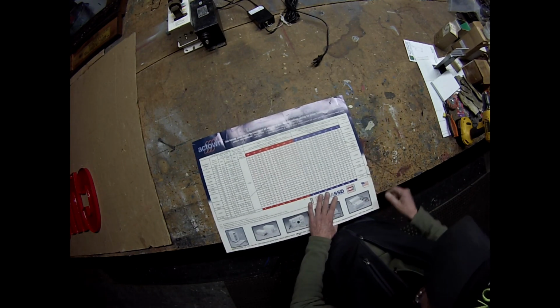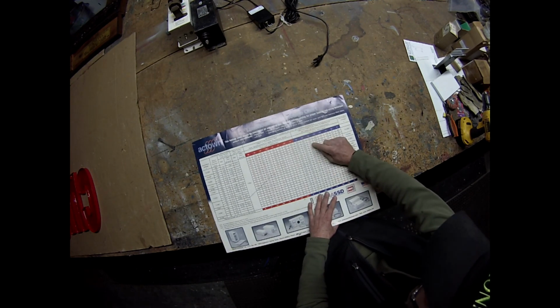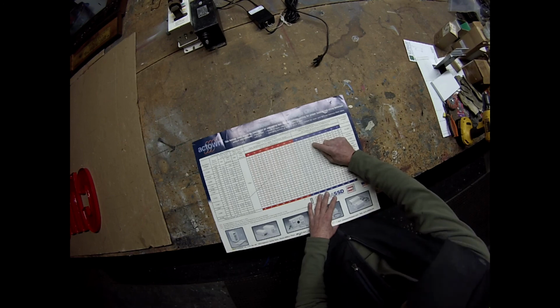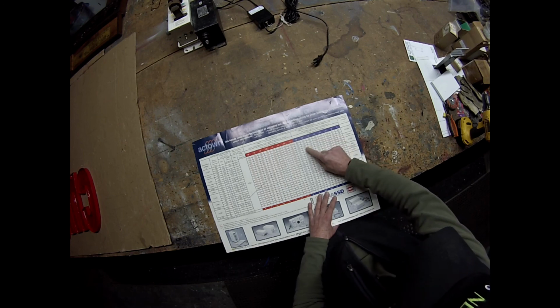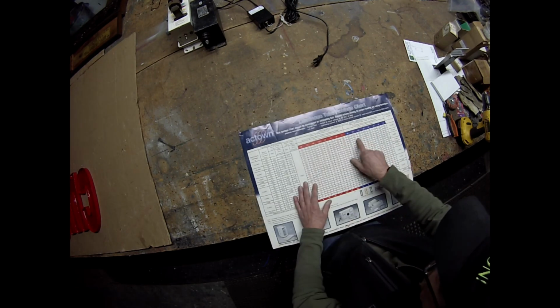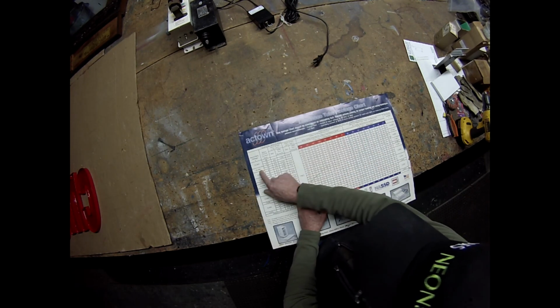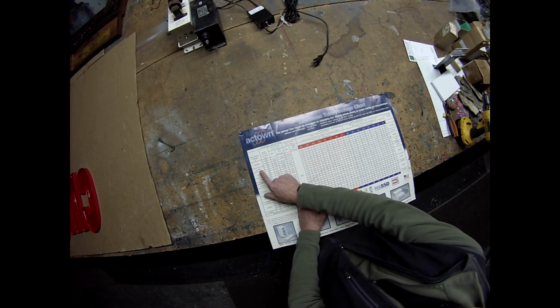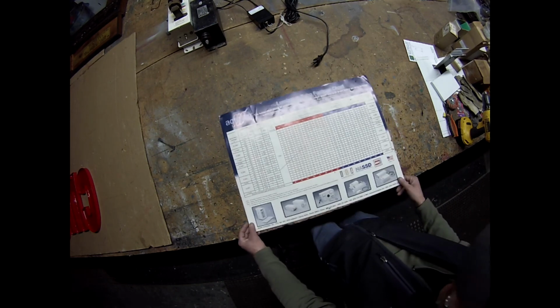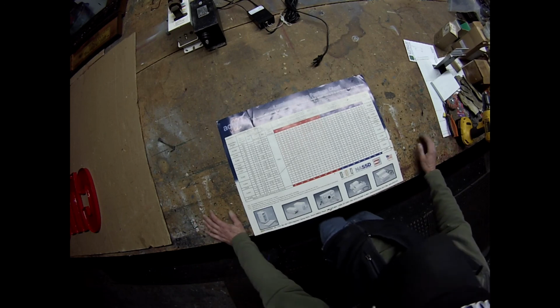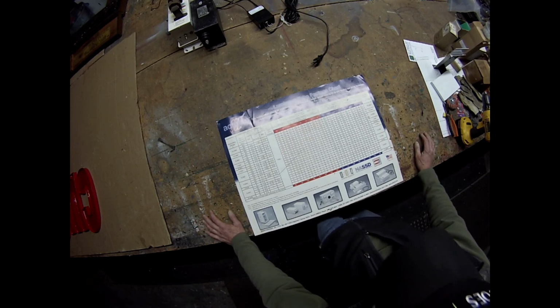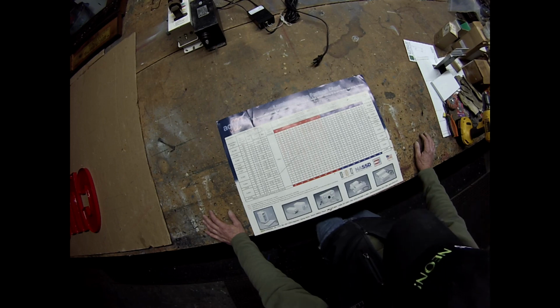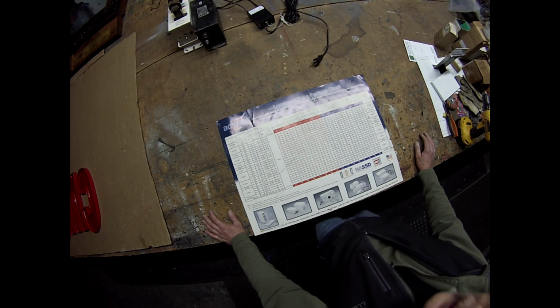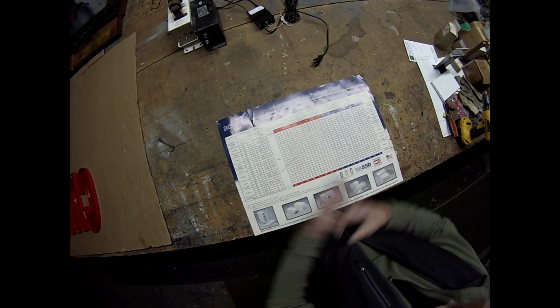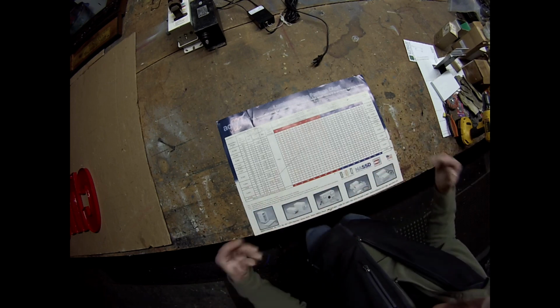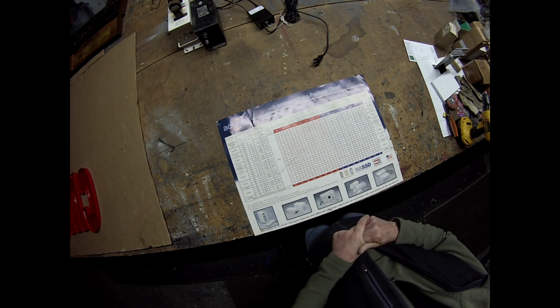Let's talk about argon. Let's say I have a 15 millimeter tube and I'm running 55 feet of glass. 55 feet at 15 millimeters. Let's walk it over. 55 feet. I'll need a 12,000 volt transformer to run that particular project. Okay? I had some questions on that: how do you determine what size transformer you use when you are illuminating a neon project? So I hope that helps a little bit to understand the difference between transformers and how you choose the proper size transformer for the project.